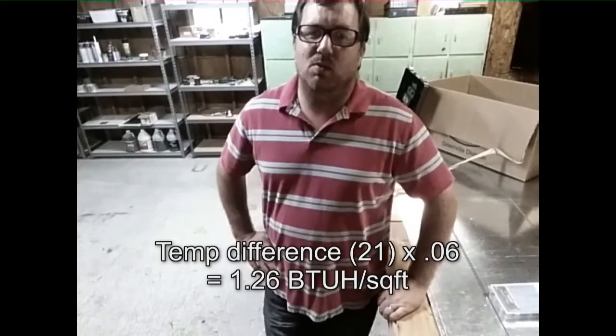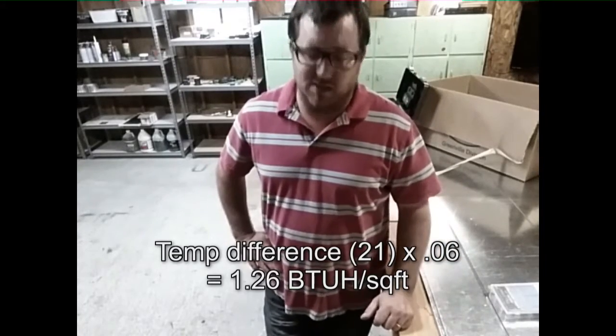But let's say we have a homeowner that says, well, I want it to be 70 degrees in my house. So you have to design equipment for that particular situation, because the design between 91 and 75 is going to be different than the design for 91 and 70. So let's say we take that 21 degrees. We're going to multiply 21 by 0.06. And let me add that up real quick in my head. So we would then get 1.26.